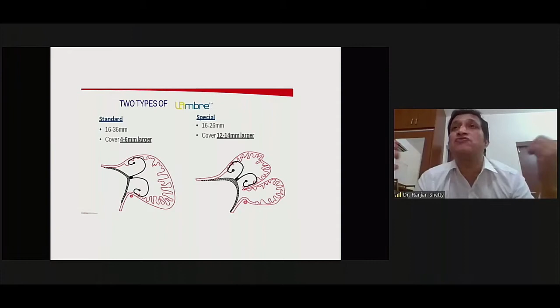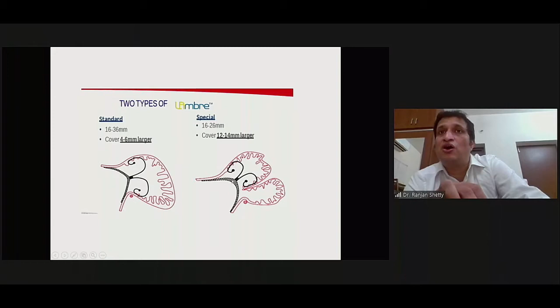The advantage of LAmbre is it would probably be suitable for 99.5% of the left atrial appendage, because any appendage it would work. So even if you have an early lobe, this is extremely difficult for any other device. If you have a lobe like this, any other device is difficult to close. But if you have an early lobe, they have what is known as special devices where the lobule of the device is smaller, but the disc is larger. So you could use the disc to cover the ostium, but use a smaller lobule to anchor into one of the lobes. So there are some options which are available.